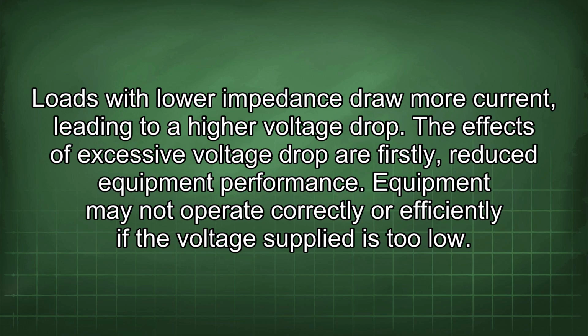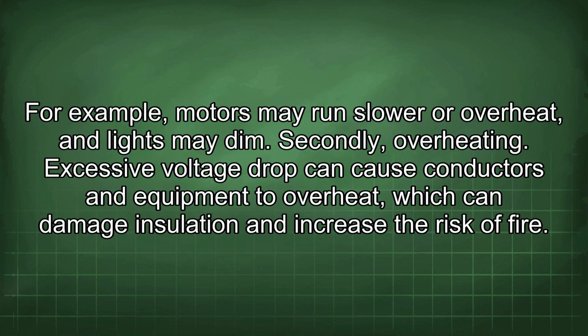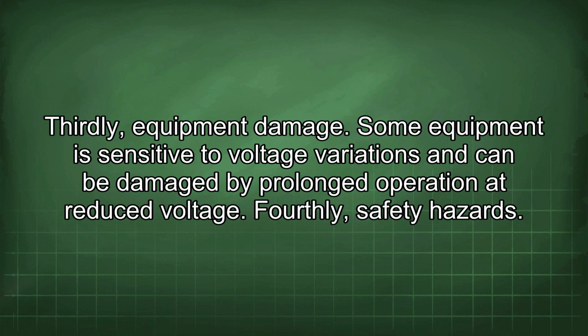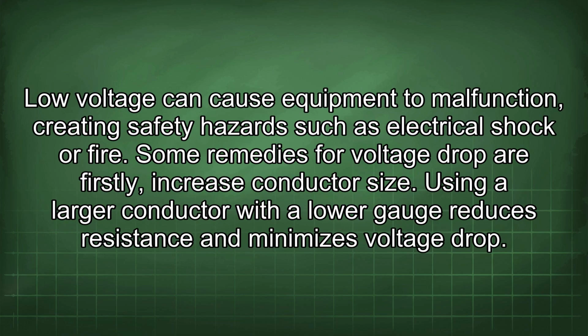The effects of excessive voltage drop are, firstly, reduced equipment performance. Equipment may not operate correctly or efficiently if the voltage supplied is too low. For example, motors may run slower or overheat, and lights may dim. Secondly, overheating. Excessive voltage drop can cause conductors and equipment to overheat, which can damage insulation and increase the risk of fire. Thirdly, equipment damage. Some equipment is sensitive to voltage variations and can be damaged by prolonged operation at reduced voltage. Fourthly, safety hazards. Low voltage can cause equipment to malfunction, creating safety hazards such as electrical shock or fire.